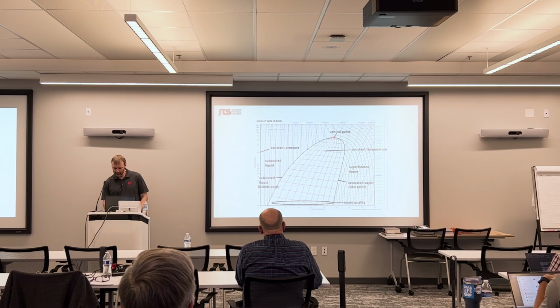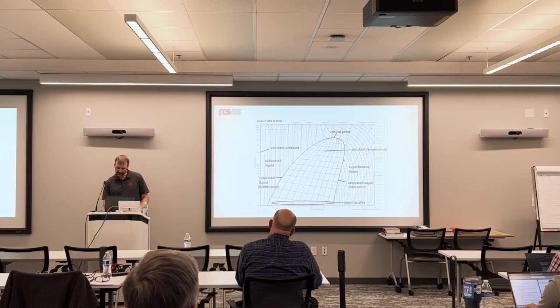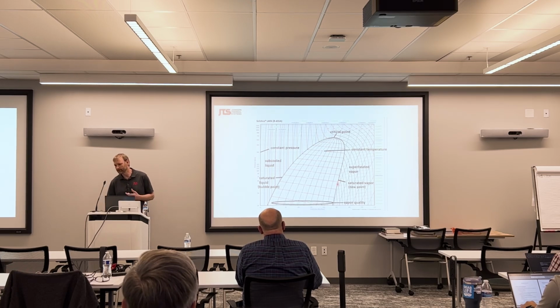Up here at the very top of the curve, you've got your critical point. With blended refrigerants, we're typically operating below the critical point. Anything to the right of the curve is superheated vapor. And right at the right edge of the curve, you have your saturated vapor, your dew point, or what's often referred to as your saturated suction temperature, will fall along this edge.